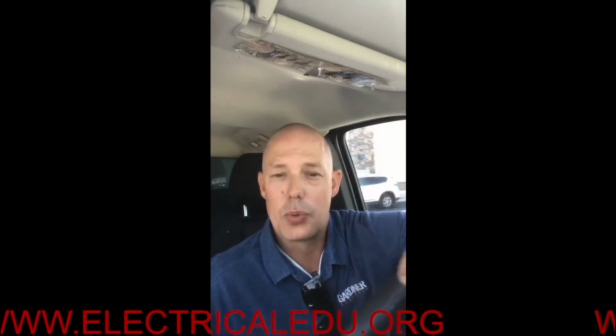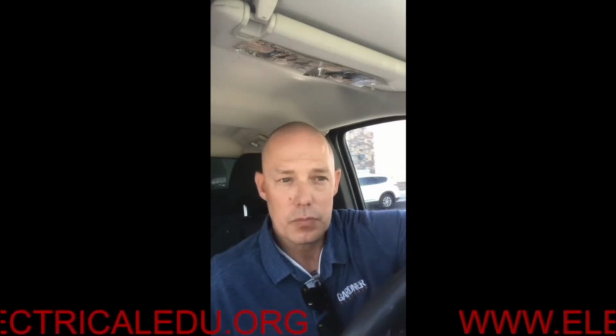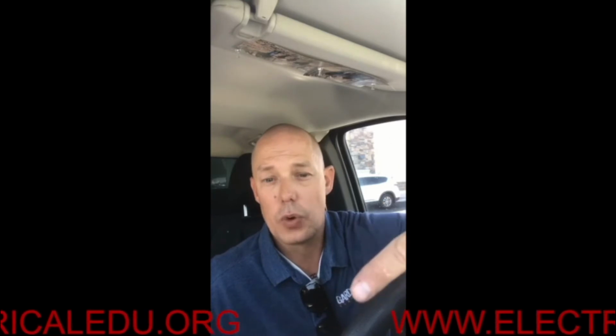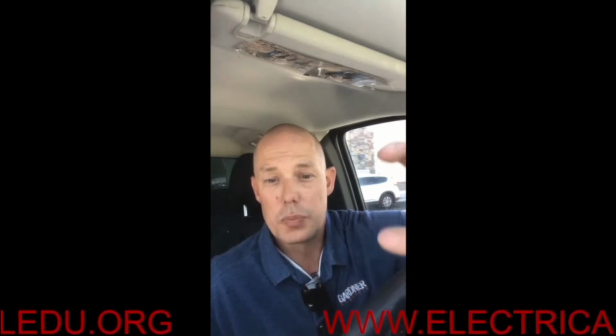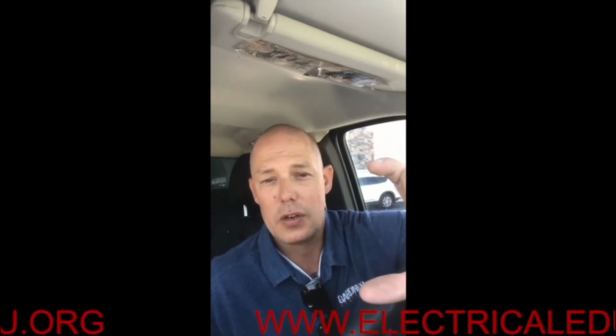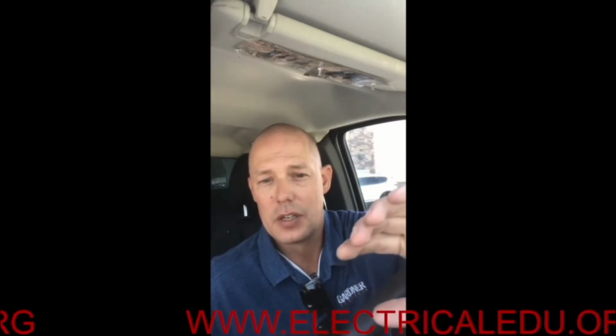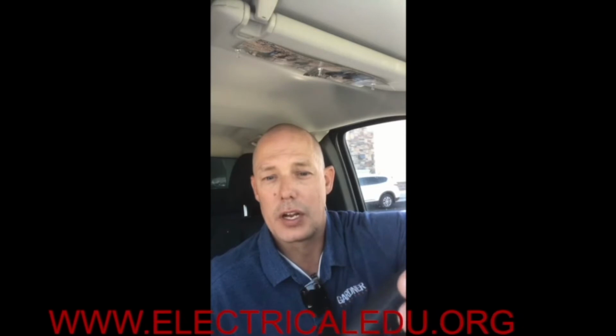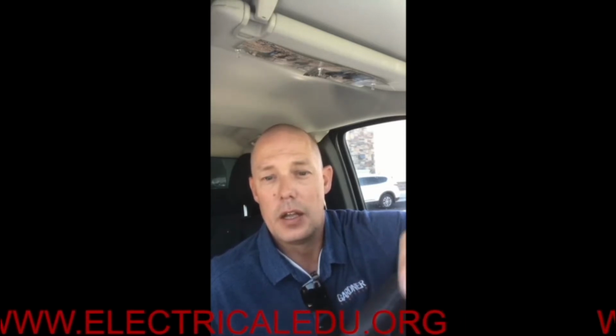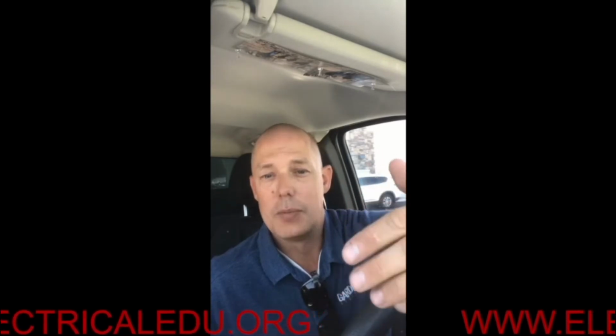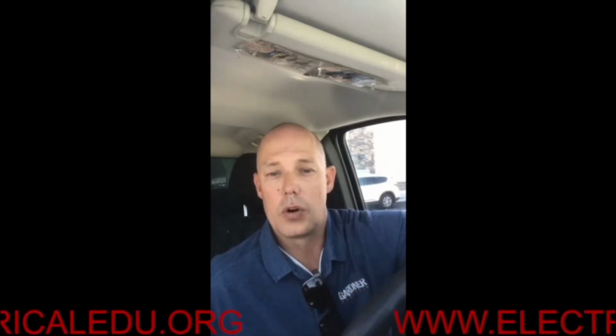And then table 310.16 in the 2020 code book. You will also have to know 240.4(G), which puts the air conditioning unit and motors and other different types of things in a whole different category, meaning you don't size the wires off your overcurrent protection device. And so that will give you reference points in that table of where to go in order to size these wires.